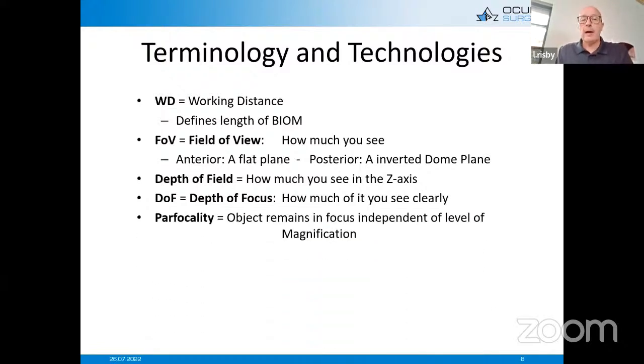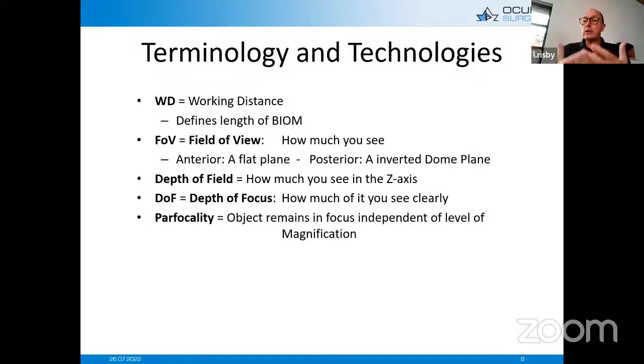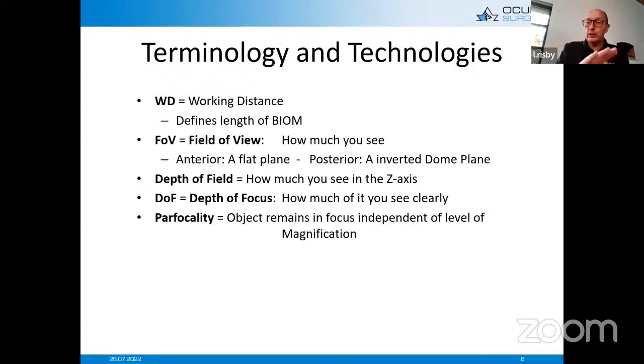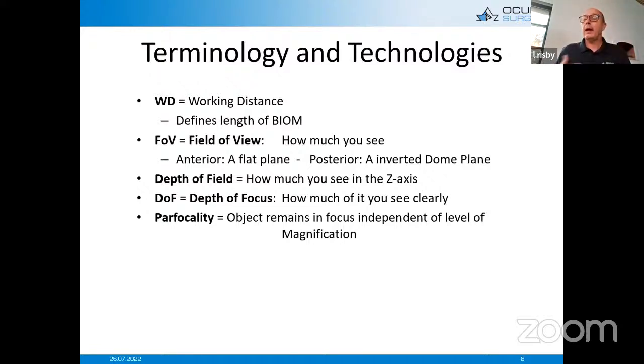The depth of field is often mixed together with the depth of focus. My depth of field is how much I can see in the Z-axis, whereas the depth of focus is how much of this depth of field I can actually see clearly in focus. You probably know the parafocality term — that means we can focus the microscope on the limbus or on the iris, then zoom in and out, and the iris stays in focus. But you have probably also experienced the opposite: focusing on the iris, zooming in, and suddenly it goes out of focus — that means it's not parafocal. Using the BIOM, I will show you why this is important.